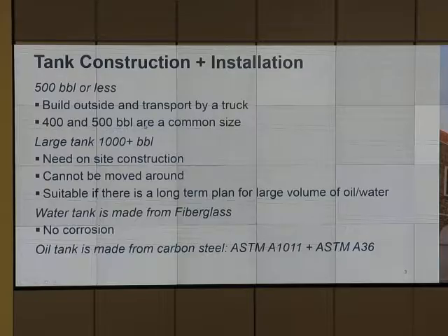Tank, 500 barrel or less, we can build outside and transport by truck. 400 and 500 barrel are common sizes. Tank larger than 1,000 barrel, we need on-site construction, cannot move around. Suitable if there's a long-term plan for the large tank.